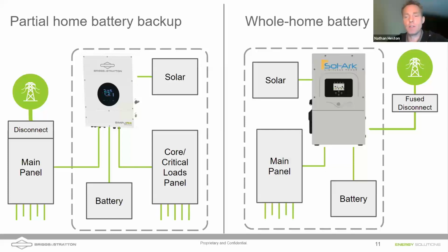On the right side of the screen, if the grid goes down, the entire loads panel stays on. The Sol-Ark is now isolated from that grid. The grid is no longer there, but we're still backing up all the loads in the house, and we do that by having a single loads panel. Note also the differences in the installations here. On the left side of the screen, we would have to install an additional panel and potentially move some loads over if we're backing up a home that currently doesn't have a critical loads panel, right?